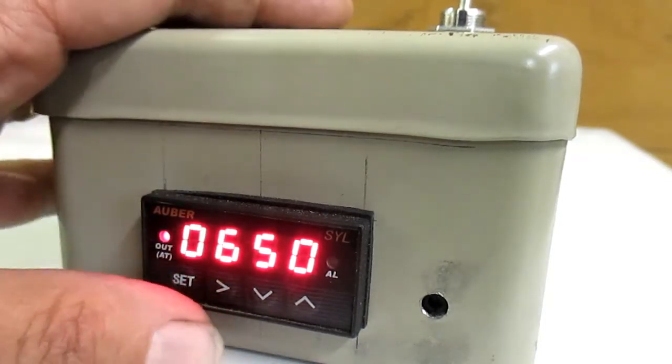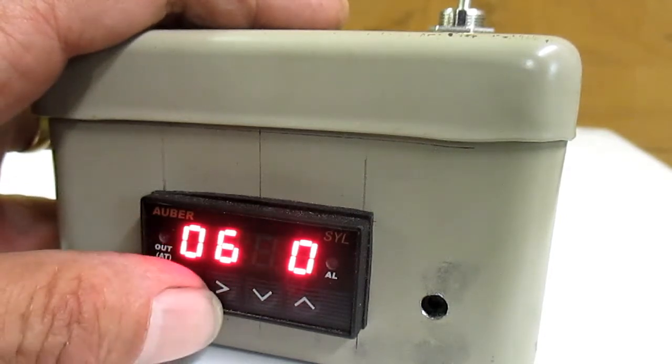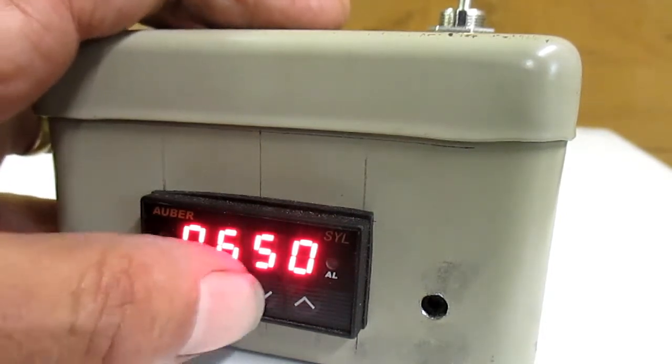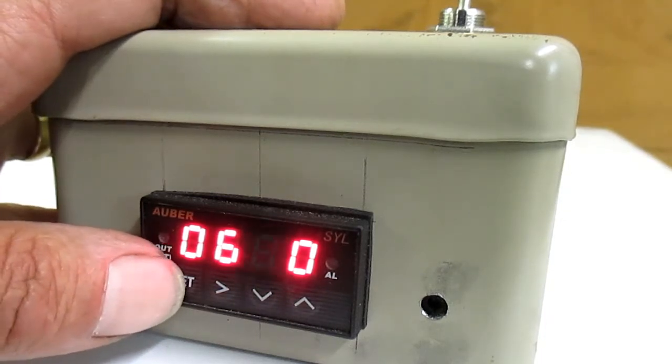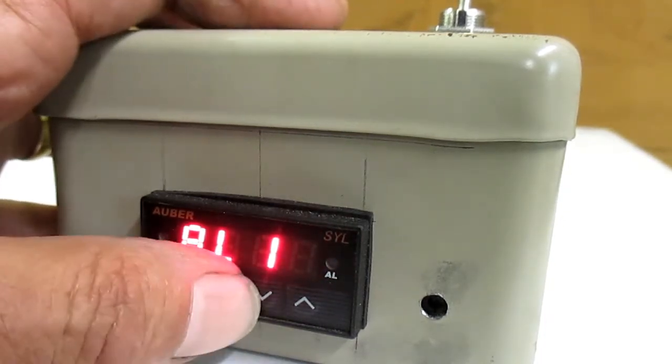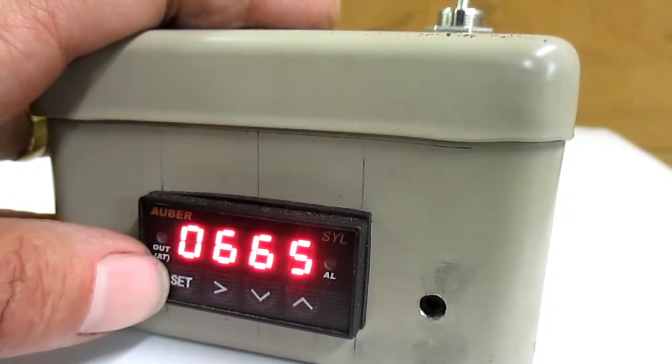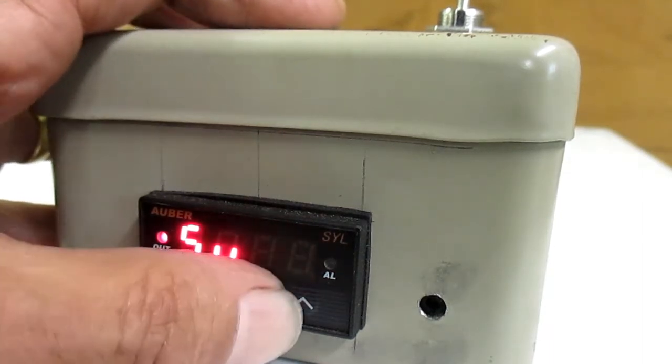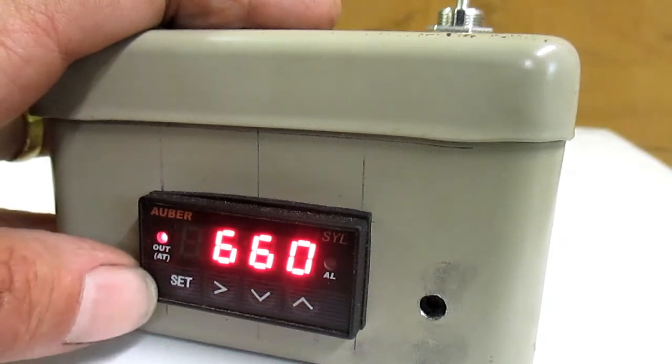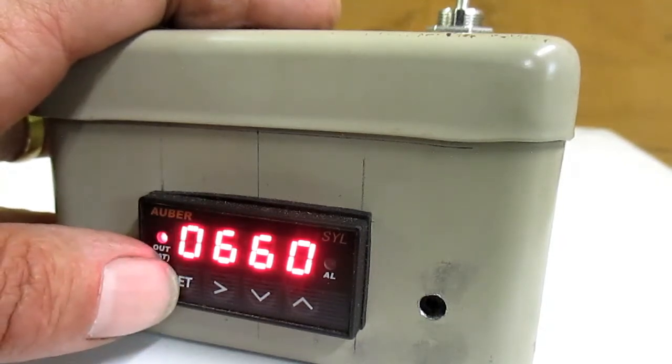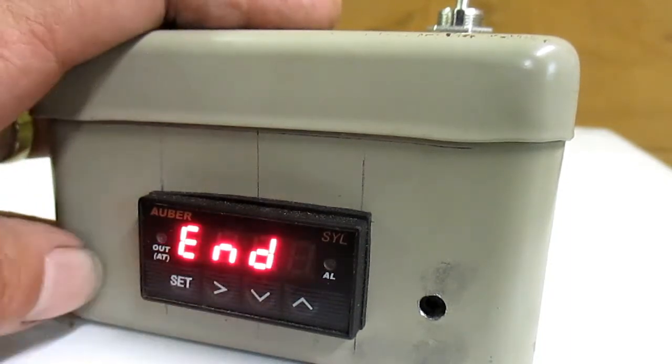All right, we're at 655. We're going to bring this up to say 665. Okay, over, over, and we'll go up one. Okay, then we press set again. Now what we're looking for is AL1, alarm low number one. So we go here, AL1. So there we are there. We had the other one set at 665. We're going to keep those numbers close and we're going to enter this at 660. So we hit set again.